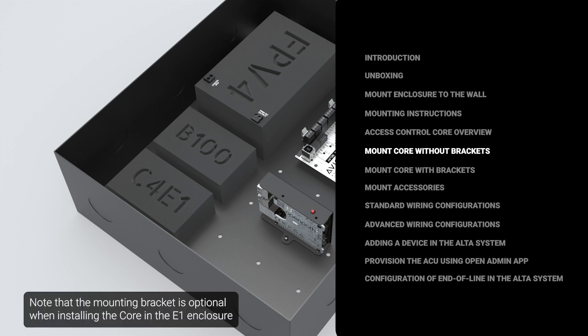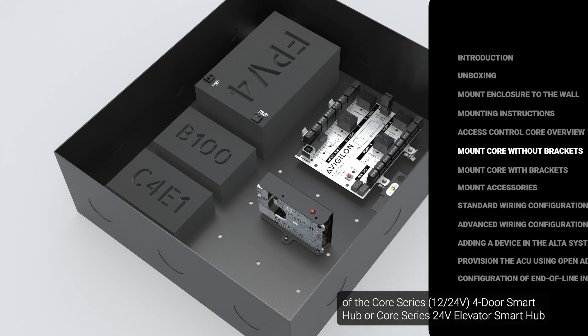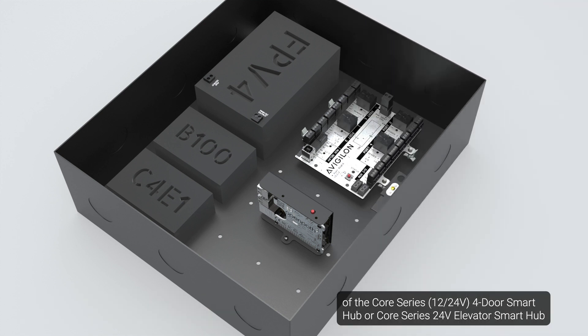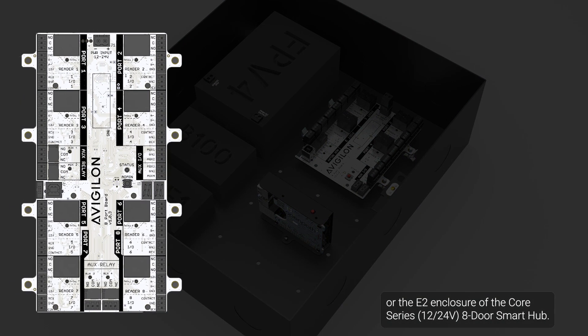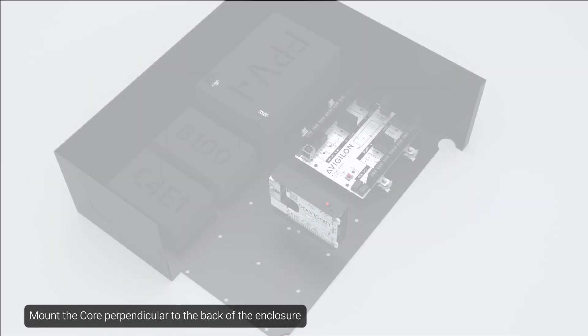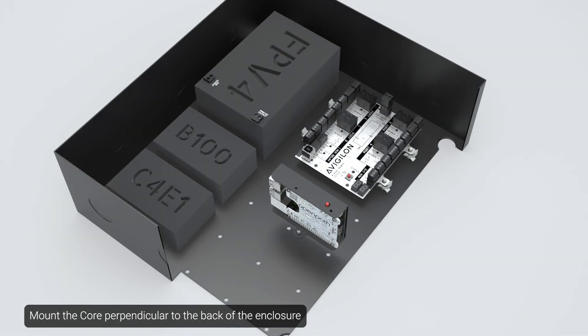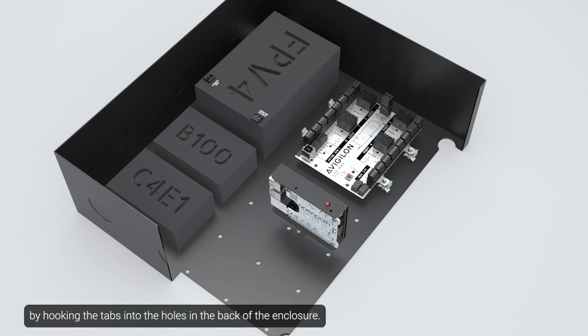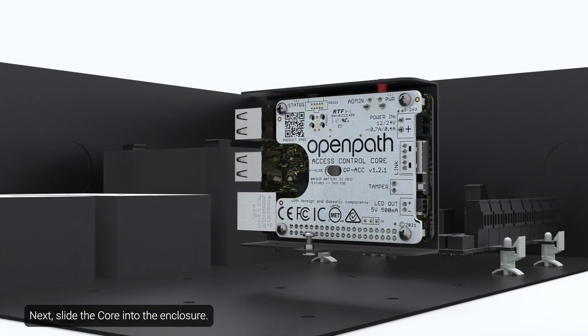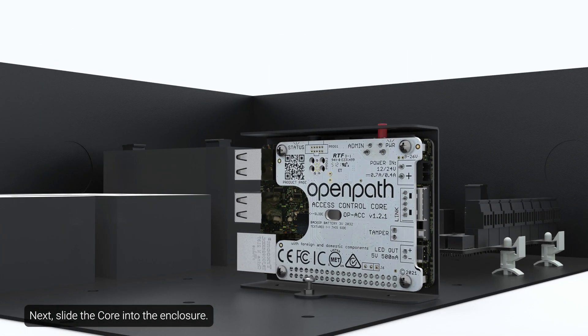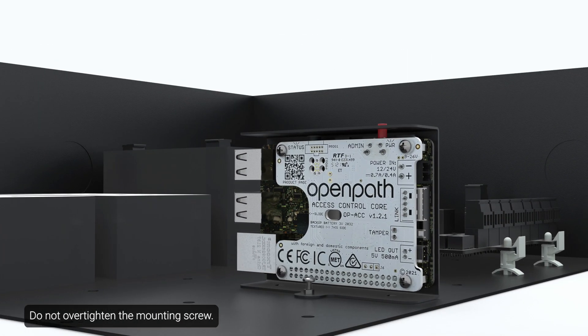Note that the mounting bracket is optional when installing the core in the E1 enclosure of the core series 4-door smart hub or core series 24-volt elevator smart hub or the E2 enclosure of the core series 8-door smart hub. Mount the core perpendicular to the back of the enclosure by hooking the tabs into the holes in the back of the enclosure. Next, slide the core into the enclosure. Then, gently tighten the mounting screw. Do not over-tighten the mounting screw.